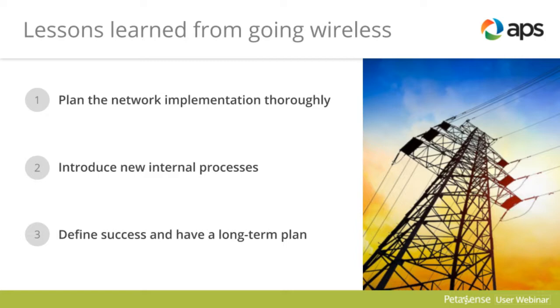We actually had a plan A, which I thought was kind of slick, but didn't turn out to work. We had located a device, basically a transformer and a pigtail with 120 volt that plugs into a photo cell socket of a streetlight. My initial plan was to install these devices on streetlights and have the boxes with the gateway and the access point up on the streetlight on the roads that go in between each of the power blocks. But when we were in those positions, we were trying to shoot a signal from that streetlight through the unit to the machines between the two units in those power blocks. All that metal attenuated the signal too much, and we were not getting a good signal.